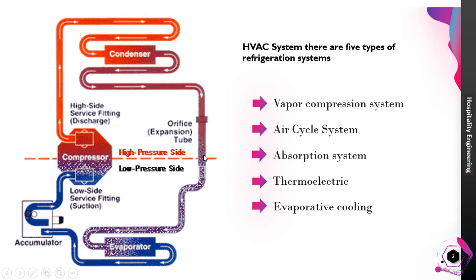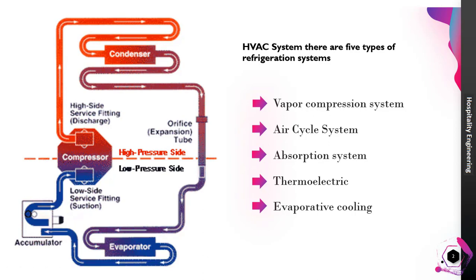While the pressure is reduced drastically as required by the evaporator, the temperature also reduces. This low-temperature saturated vapor comes into the evaporator, where it starts to evaporate by cooling the chilled water. This evaporator gas, when it comes out, becomes the dry, low-pressure, low-temperature gas, which is collected in the accumulator. From the accumulator, this low-temperature, low-pressure gas goes back to the compressor, and thus the cycle continues in the Vapor Compression System.